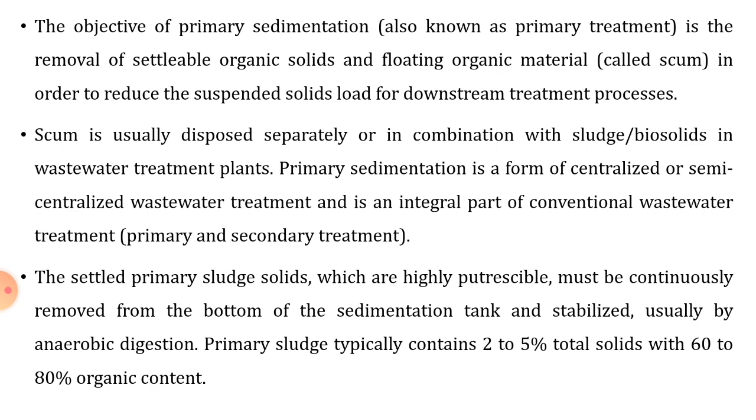The settled primary sludge solids, which are highly putrescible, must be continuously removed from the bottom of the sedimentation tank and stabilized, usually by anaerobic digestion. Primary sludge typically contains 2 to 5% total solids with 60 to 80% of organic content. So whatever primary sludge gets accumulated in the sedimentation tank contains 2 to 5% of total solids with 60 to 80% of organic matter. So very high organic content is there in the sludge which is settled in the sedimentation tank, where it will start stabilizing.